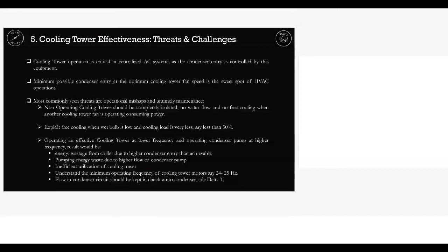So we do all this analysis, we get leverage on the data. If we know the data, we can identify when maintenance needs to be done, when the cooling tower fills need to be cleaned, when the water quality needs to be checked, when the machine needs to be descaled. So all these insights or intelligence onto the data and the equipment, we get through these parameters of approach or condenser entry temperatures, all these things. I'm not making this too much data or too much process, but this is some theory you should understand, that's why I'm going through it.